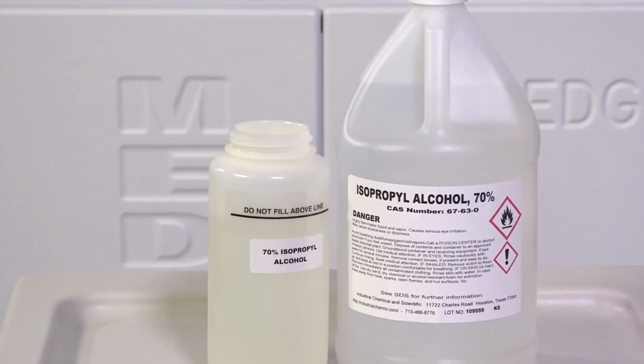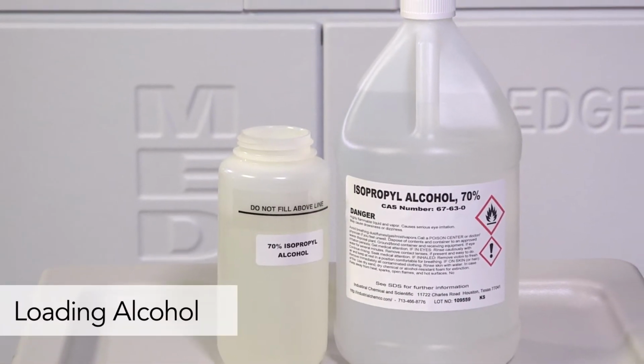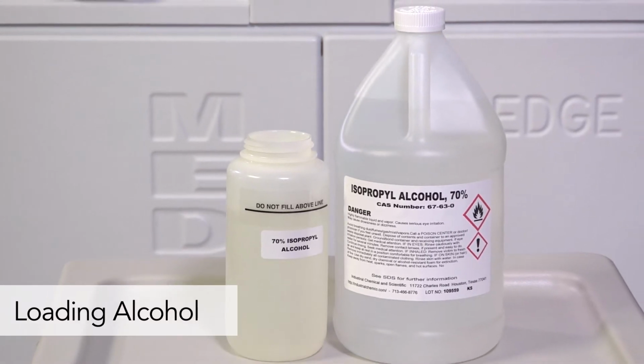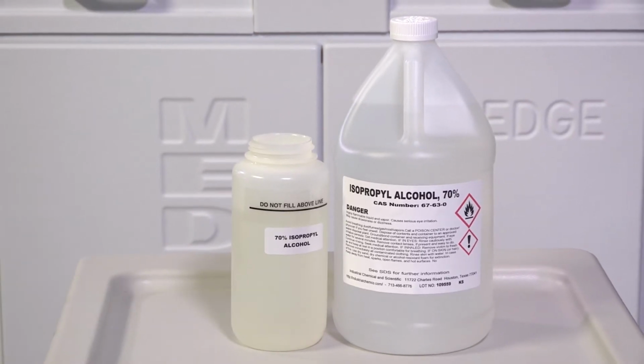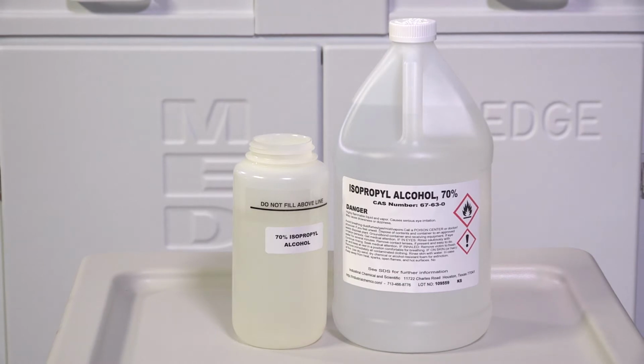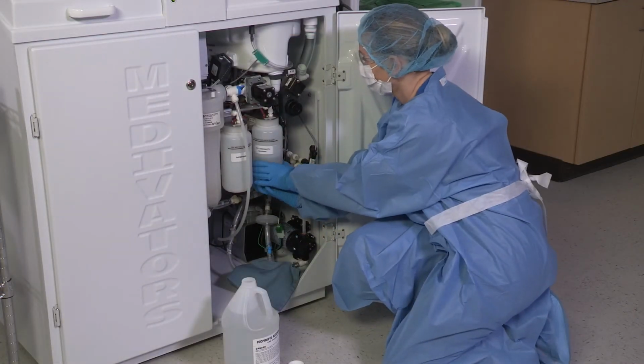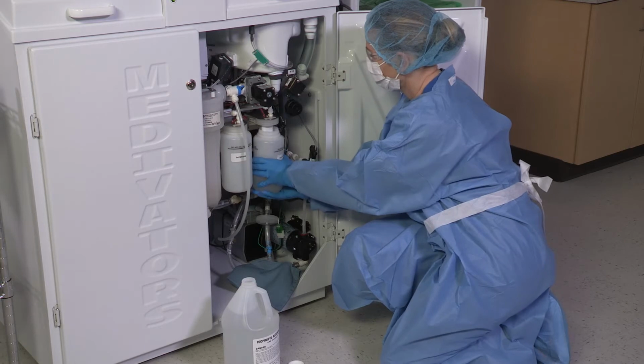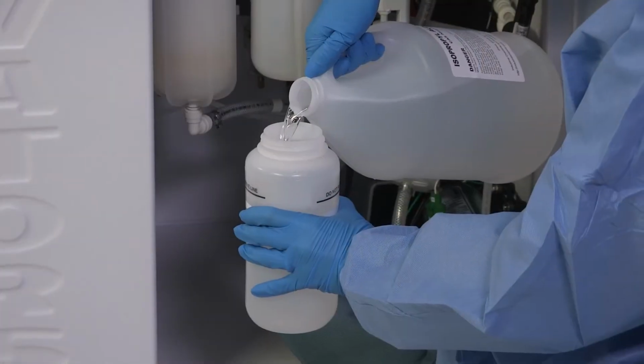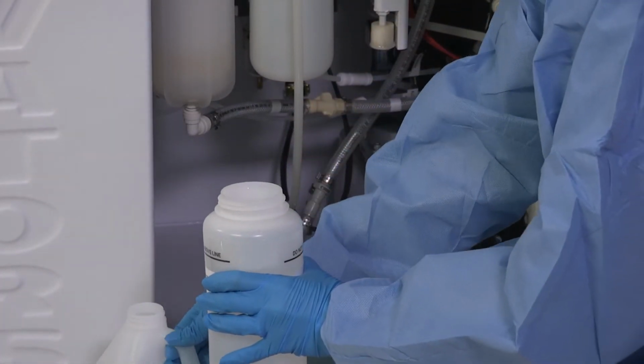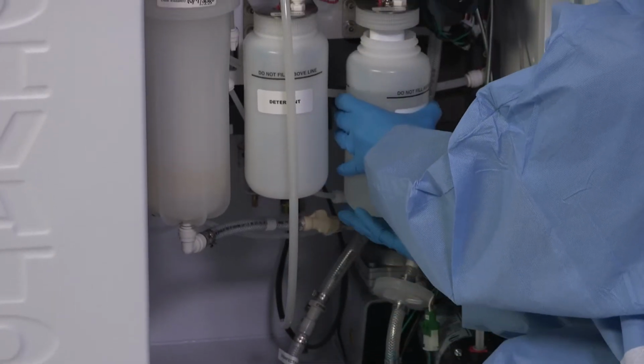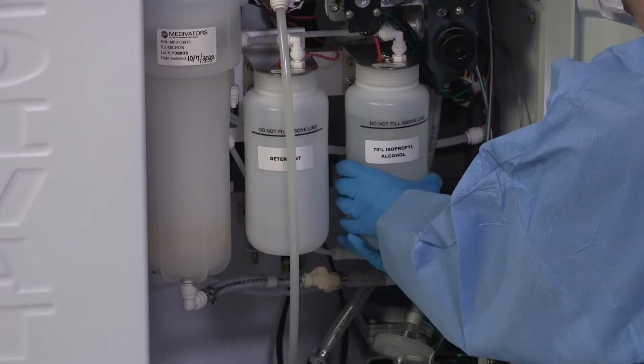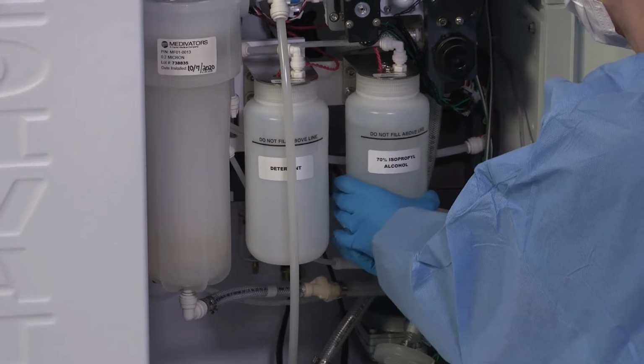For the alcohol phase of the disinfection cycle to be completed, sufficient alcohol is needed in the reservoir. As part of the daily maintenance, check the alcohol level in the reservoir. If low, replace the 70% isopropyl alcohol by twisting the alcohol reservoir in a counterclockwise direction to remove. Add alcohol to the refill line indicated on the reservoir, which is 800 milliliters. The alcohol level will rise above the fill line when the reservoir is replaced.